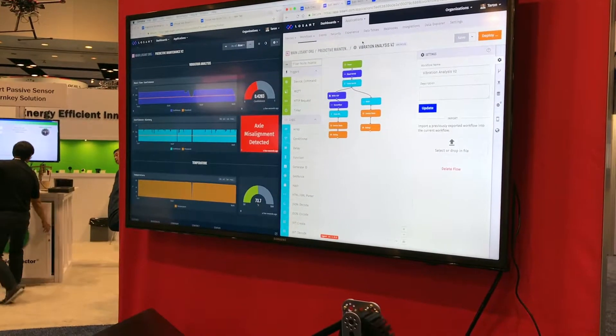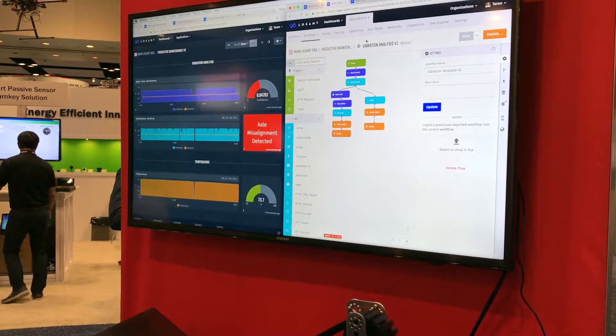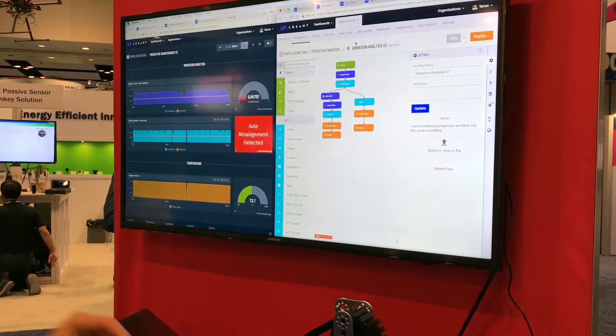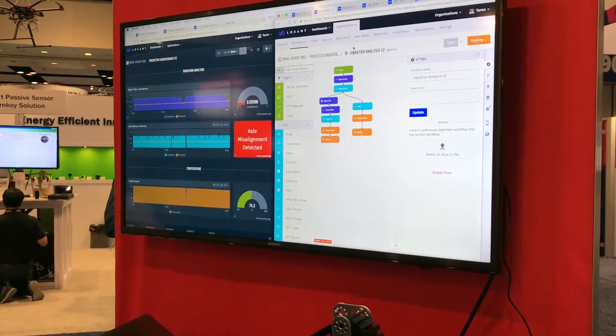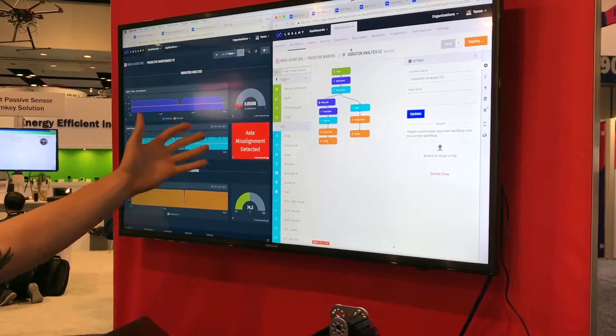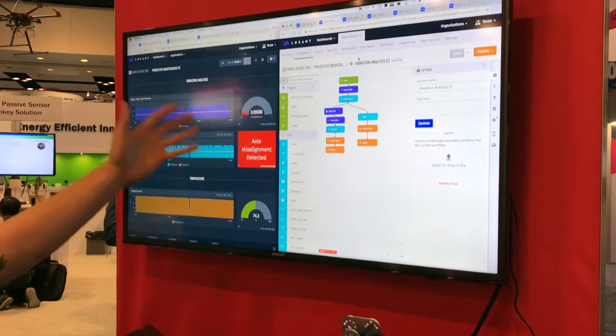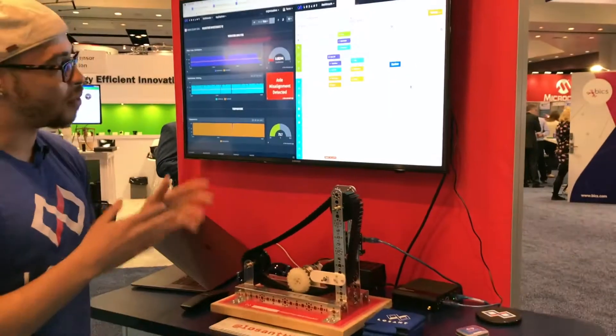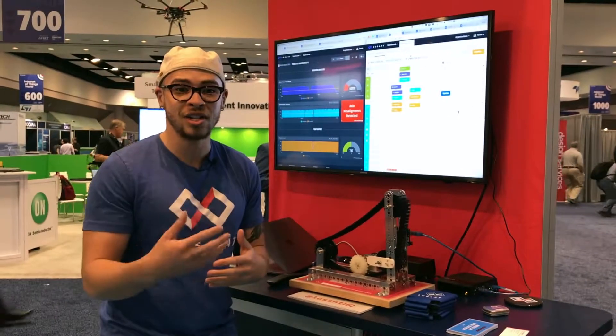This workflow is running on this edge device. What this workflow is doing is every five seconds it's reading sensor data from the vibration sensor — about 3,000 data points — the kind of data you don't want to send to the cloud. Then we're executing the machine learning model locally and sending that confidence level up to the cloud. So here we can see that our axle has now been misaligned and we can detect that.